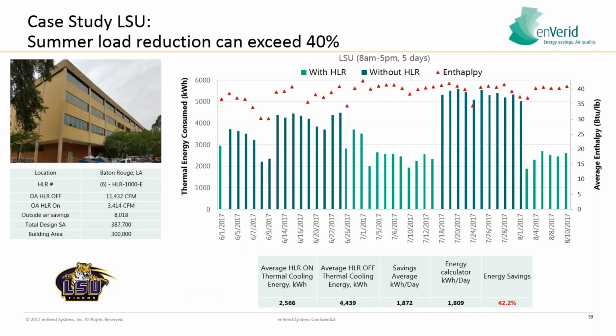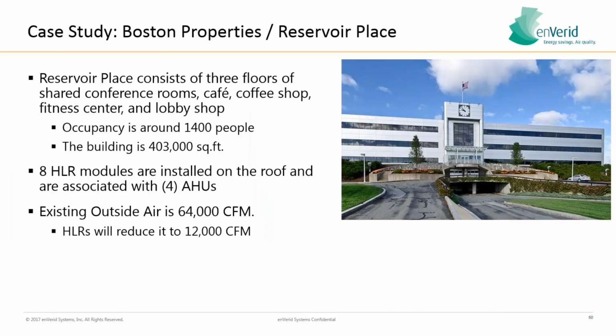One example of this is at LSU, where one day this system actually showed a spike in VOCs, and the net result there was that we found out that they were painting with a VOC-laden paint. So we were able to specifically address it with the field team in real time. We were able to call them and say, hey, there's a VOC spike. We're monitoring the system. Everything's fine on our side. What are you guys doing? And they said, oh, we're painting, but whoops, we used the wrong paint. So kind of a cool application there, 40% plus energy savings.